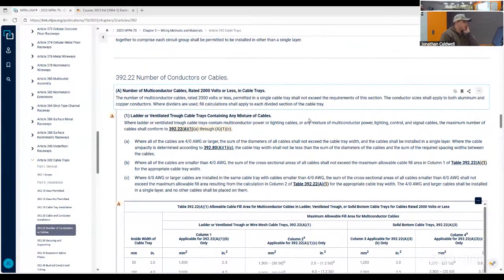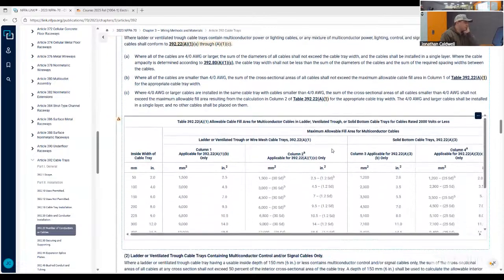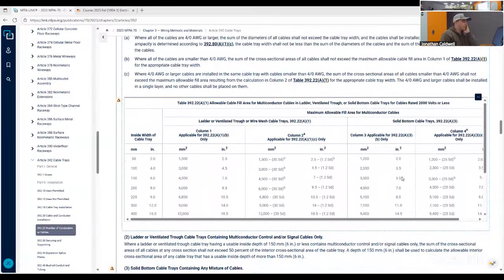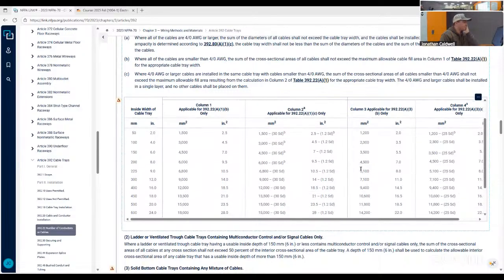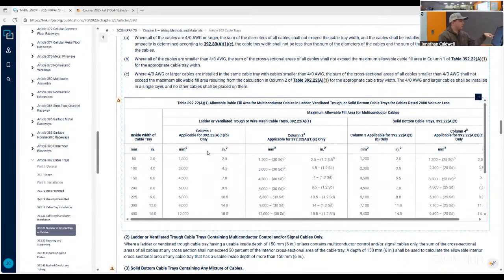And then this is just the number of conductors and cables, and then this has your load calculations essentially. The key word here is inside width of the cable tray, not outside dimensions. And if you're using cable tray like we do, there's essentially two C channels on the sides, and then there's rungs in between that hold it all together. So the inside of the C channel from top of the rung is your load capacity. That makes sense.